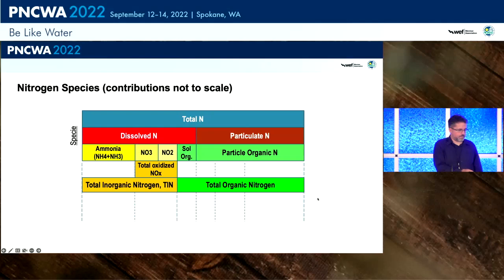The process in place — the four-stage Bardenpho — utilizes standard biological nutrient removal for nitrogen. We're focused on two species. As we bring the plant up to full commissioning, we need to keep in mind the differences between our nitrifiers — which are going to set the SRT of the plant. They're slow growers, sensitive to temperature and toxicity, so they'll be critical for us to maintain stable nitrification as we move the plant into full BNR. And of course you have the denitrifiers, which are more robust in one sense, but you have to be careful of substrate limitations.